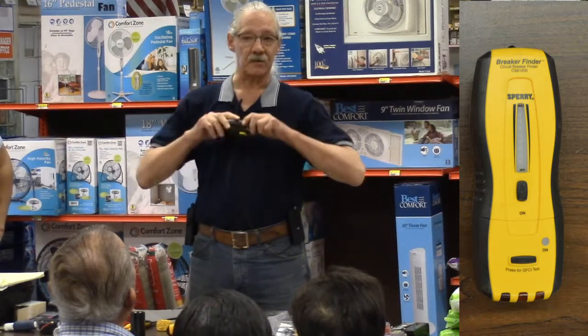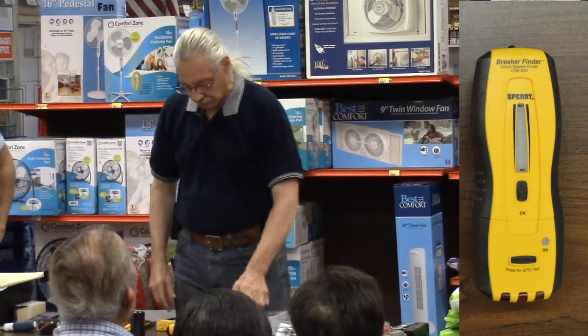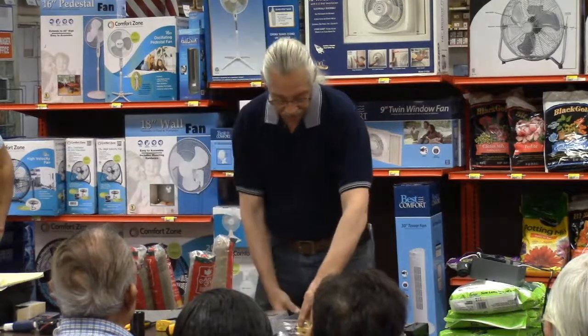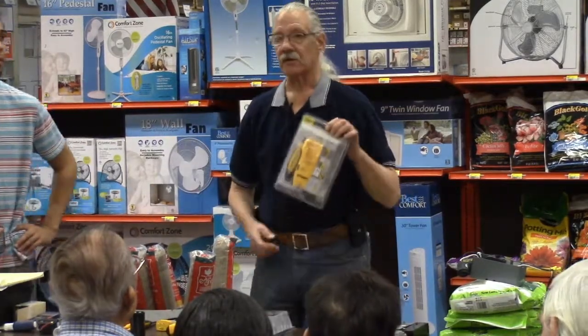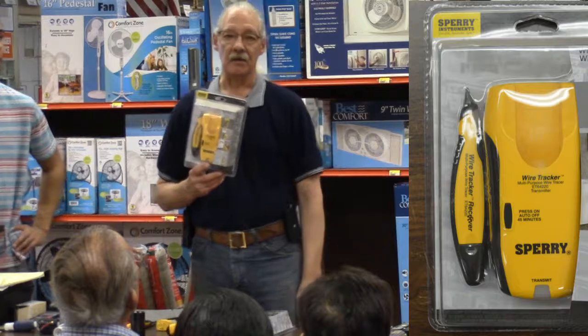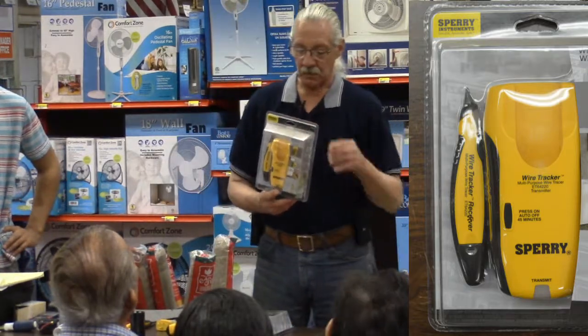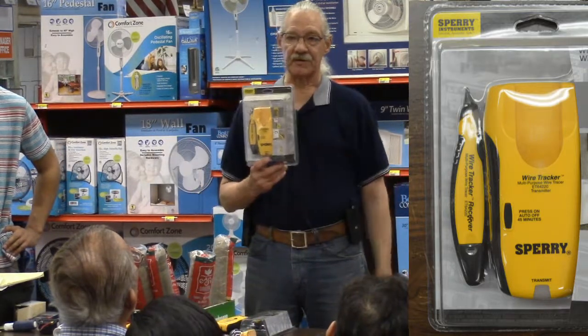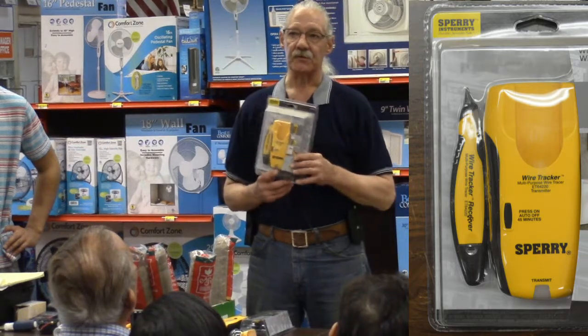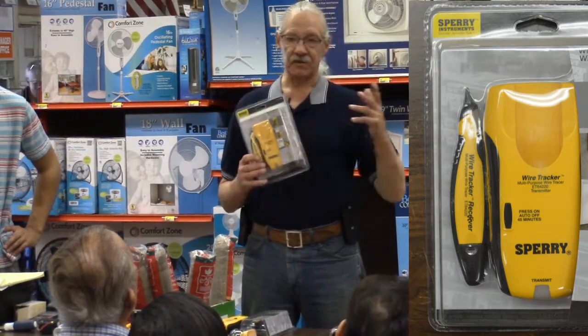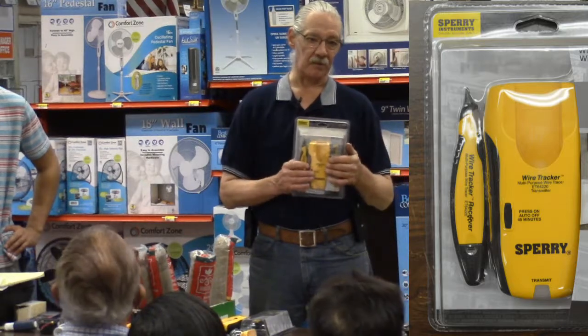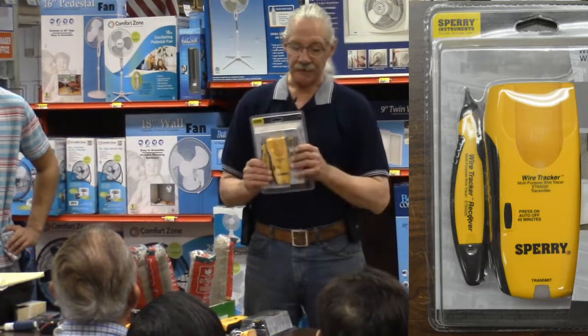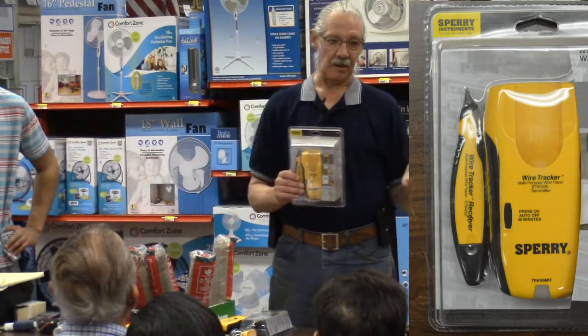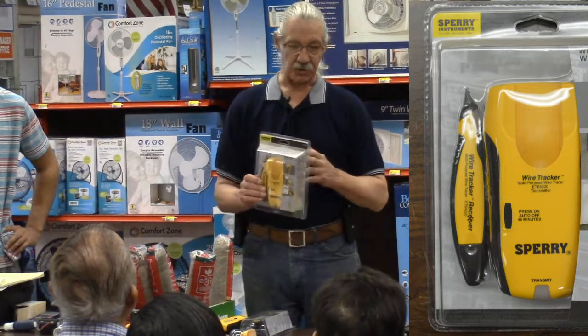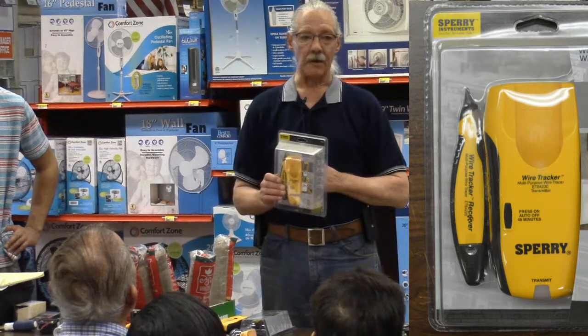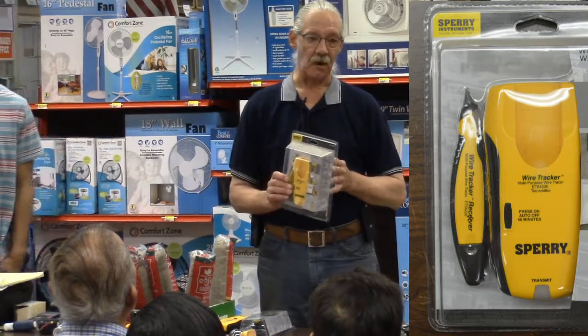This is for energized circuits, by the way. This tester is known as a wire tracker for non-energized circuits. We don't use it that much in basic electricity - it's more used for speaker cable, coax TV cable, and those type of cables, computer cabling that normally isn't in conduit and can be tracked through the wall because it's bare wire and not shielded with a ground.